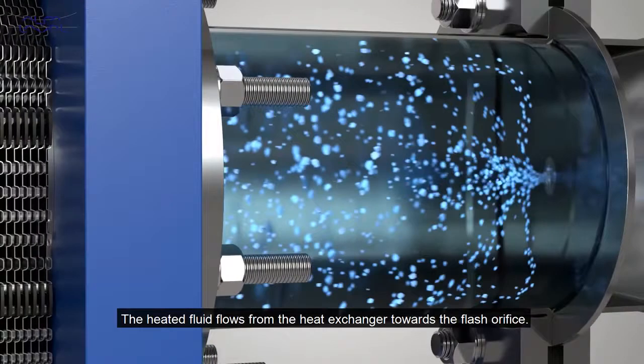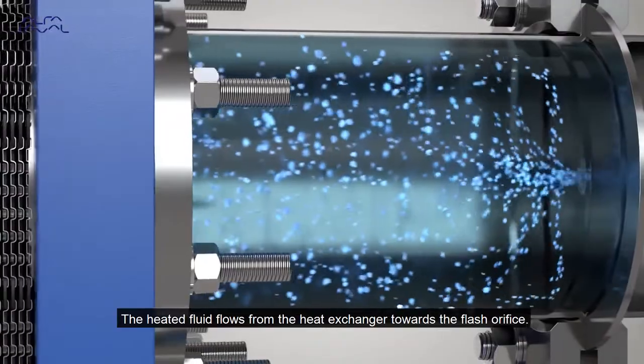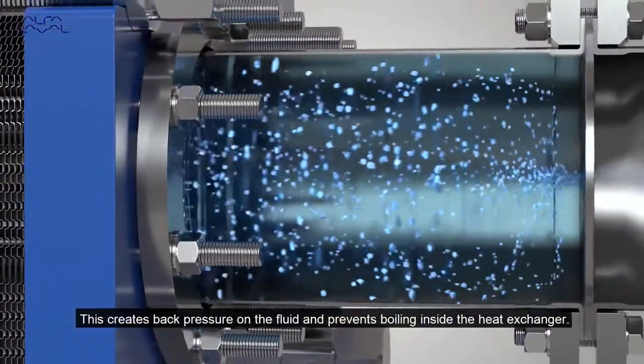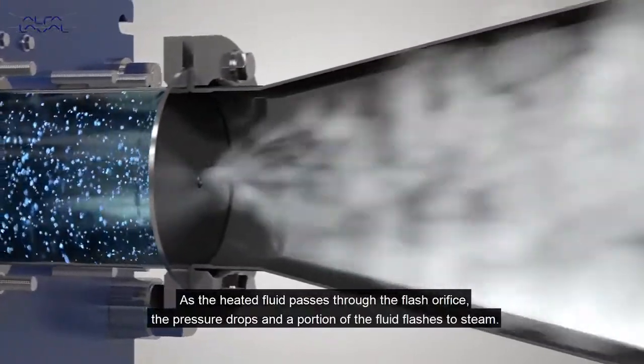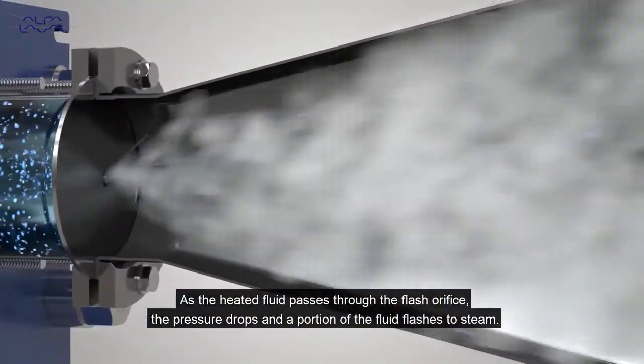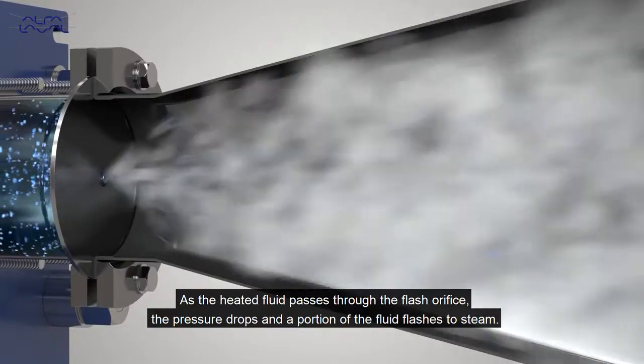The heated fluid flows from the heat exchanger towards the flash orifice. This creates back pressure on the fluid and prevents boiling inside the heat exchanger. As the heated fluid passes through the flash orifice, the pressure drops and a portion of the fluid flashes to steam.